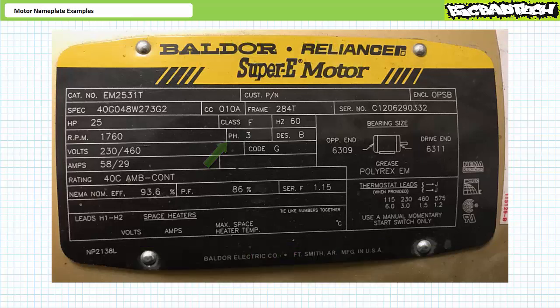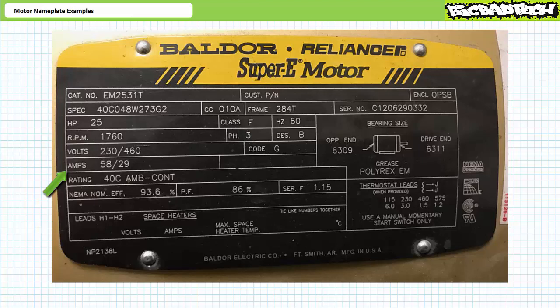It looks like this is a three-phase motor intended to operate at 60 Hz. It appears to be a dual voltage motor that can operate at 230 volts in the low voltage configuration and 460 volts in the high voltage configuration. In the low voltage configuration it draws 58 amps at rated condition, whereas in the high voltage configuration it draws only 29 amps. At rated condition it has a power factor of 0.86, operates at 93.6% efficiency, and the inrush code appears to be G.